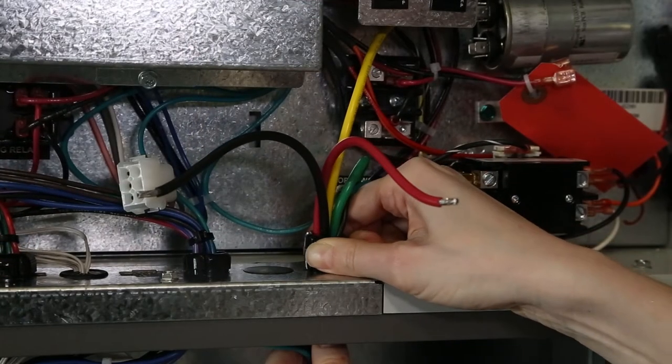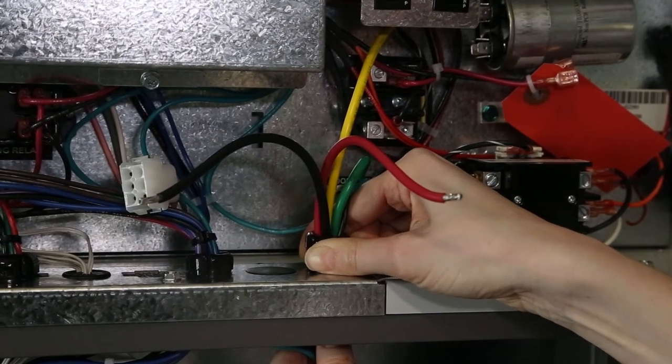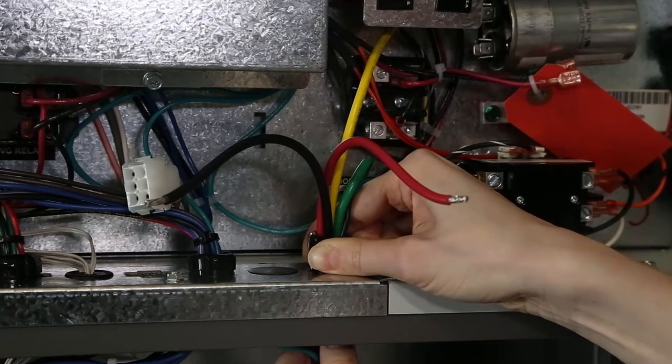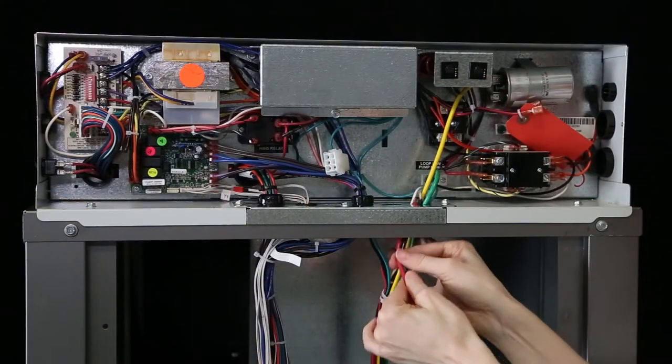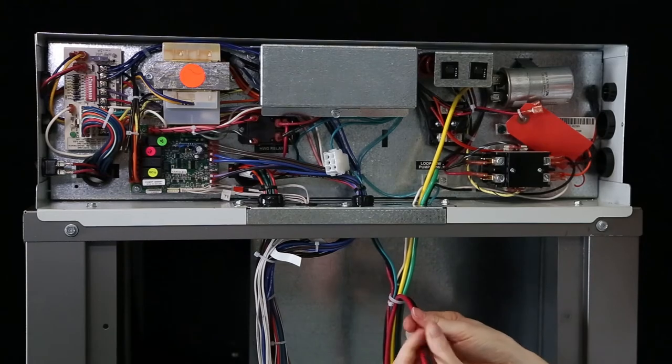At this point the strain relief that snugly holds all the high voltage compressor wires is removed from the control wiring plate that is mounted on the top cover of the unit so that the red and black wires can be separated from the bundle and routed down to the compressor section.